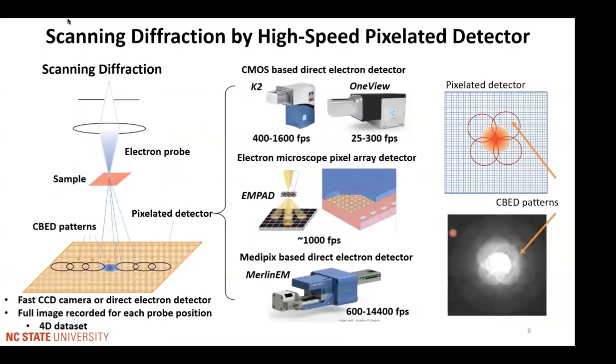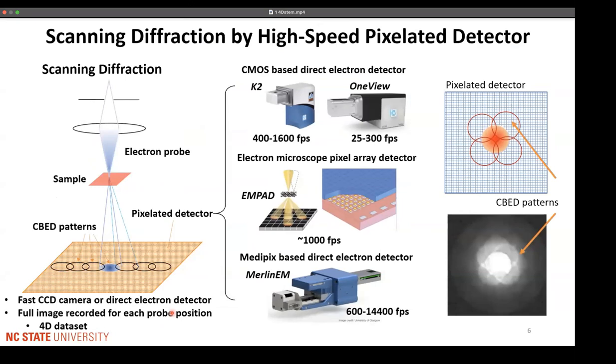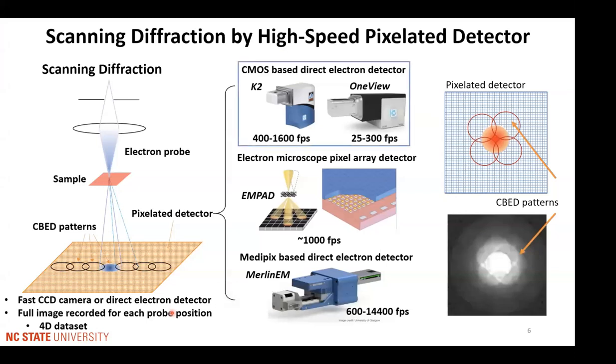The obstacle in 4D STEM is the speed, because you will need to take nice diffraction at each probe location to get a map, which was quite time-consuming and can challenge the sample and instrument stability. Recent advances in instrumentation now enable 4D STEM to be taken in aberration-corrected STEM at high spatial resolution with high frequency. For example, the Gatan K2 camera can run at a speed of a thousand frames per second. An EMPAD detector designed at Cornell also offers a thousand frames per second acquisition of images with high dynamic range. MerlinEM can run up to 10,000 frames per second.